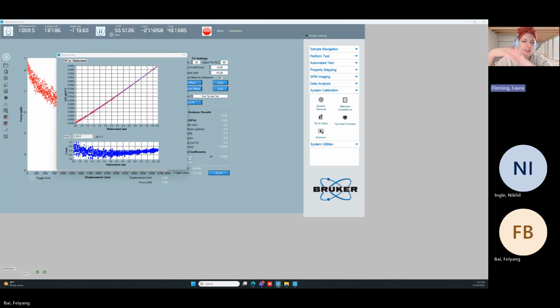Okay, so it actuated, it went from 0 to about 4 microns. We're fitting from 0.8 to 3.6. The red line of travel looks appropriate. There's a small noise that is standard for this system, but there's no discontinuities or large random noise issues happening. The blue line of travel follows well. So all of this looks good. So we can go ahead and click yes, and then we can close this plot. I think your yes is on your other screen, that pop-up. Yes. I remember that from last time.